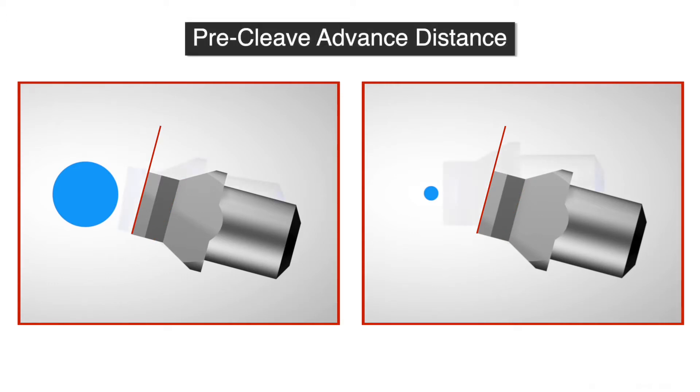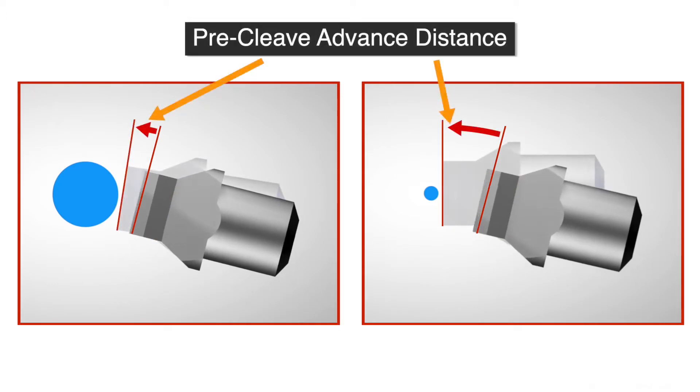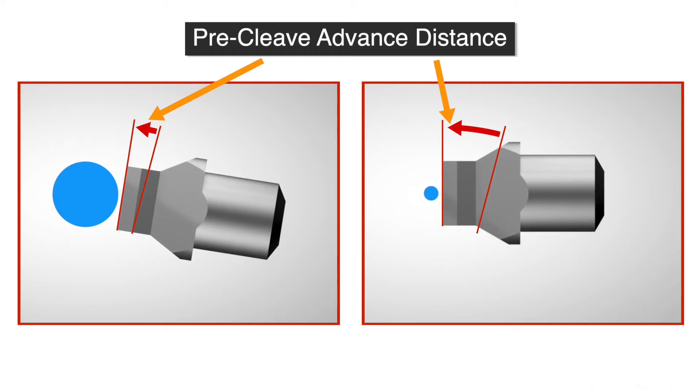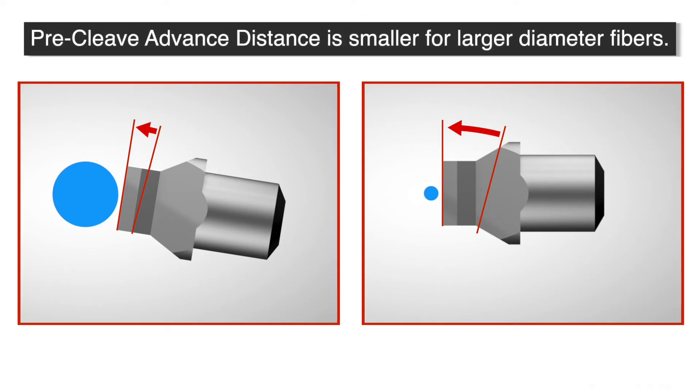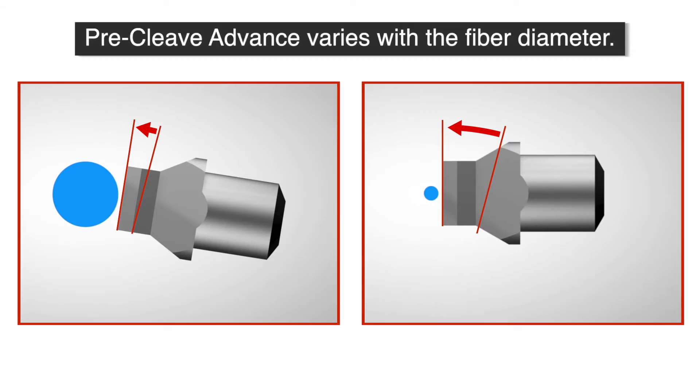The pre-cleave advance distance is the distance the blade moves forwards from the blade offset distance towards the fiber. It is modified to account for the fact that for larger fibers, the blade needs to move a smaller overall distance from home to reach the fiber. The pre-cleave advance value is therefore specific for a particular fiber size and cleave file.